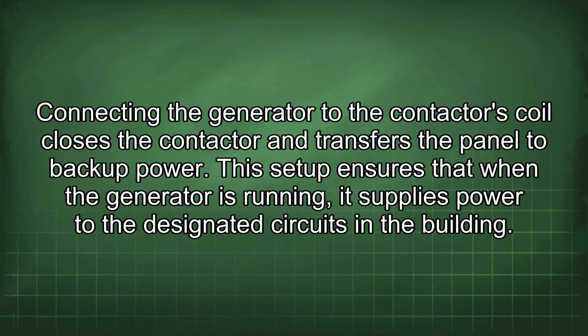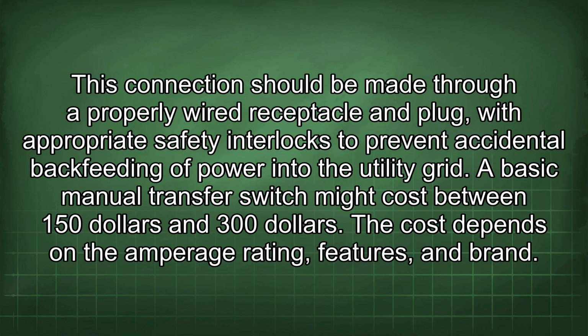Connecting the generator to the contactor's coil closes the contactor and transfers the panel to backup power. This setup ensures that when the generator is running, it supplies power to the designated circuits in a building. This connection should be made through a properly wired receptacle and plug, with appropriate safety interlocks to prevent accidental backfeeding of power into the utility grid.